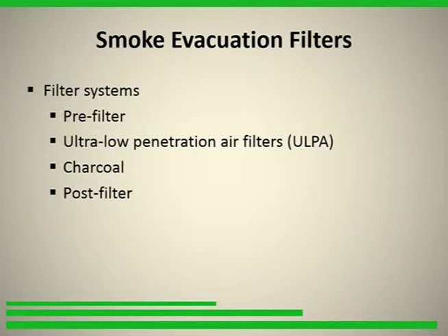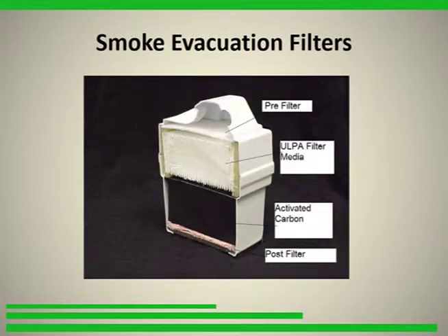These ULPA filters, next slide please, sort of look like this. They have a pre-filter material, the actual ULPA filter, which is usually a microfiber glass material, although one company has its own proprietary filter material. The activated charcoal absorbs the chemical odors and the chemicals themselves, and then there's a small post filter before the filtered smoke leaves the filter back into the operating room.